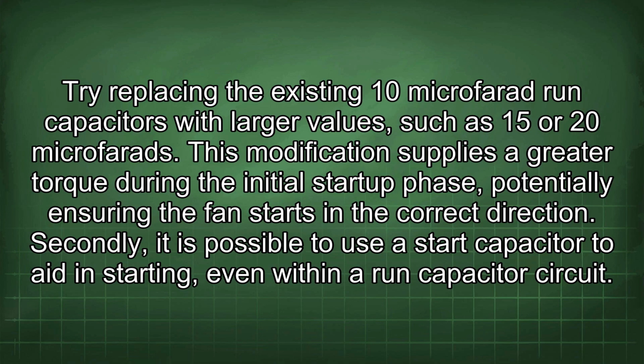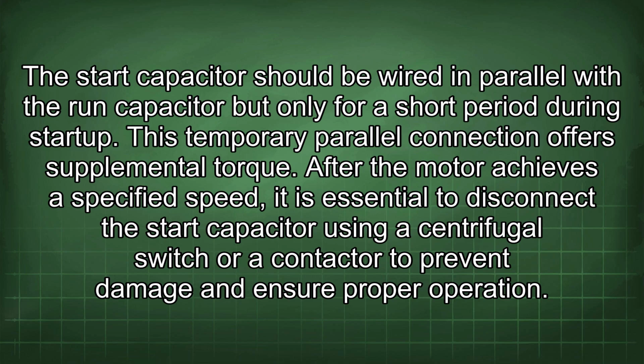This modification supplies a greater torque during the initial startup phase, potentially ensuring the fan starts in the correct direction. Secondly, it is possible to use a start capacitor to aid in starting, even within a run capacitor circuit. The start capacitor should be wired in parallel with the run capacitor, but only for a short period during startup. This temporary parallel connection offers supplemental torque.